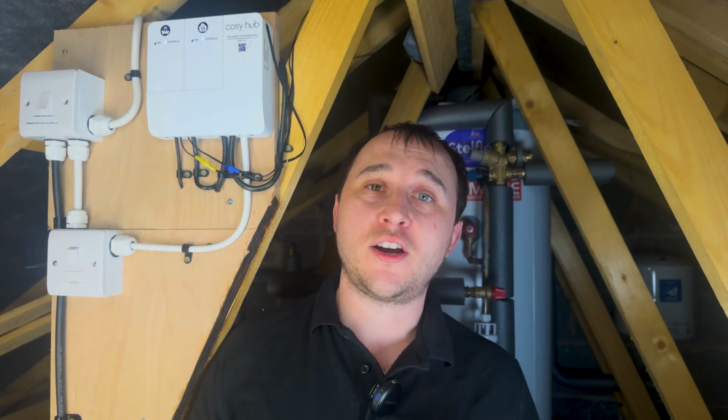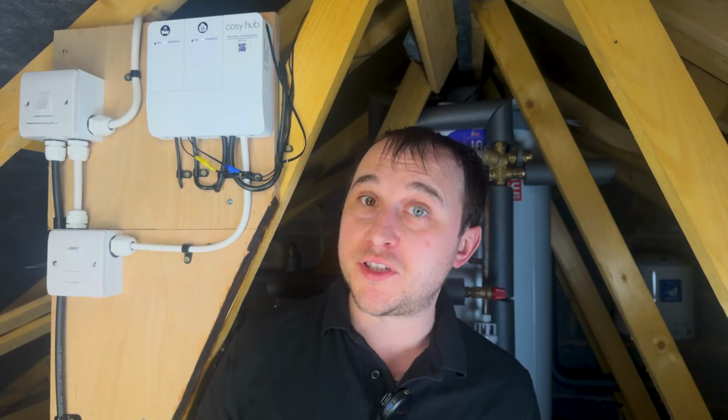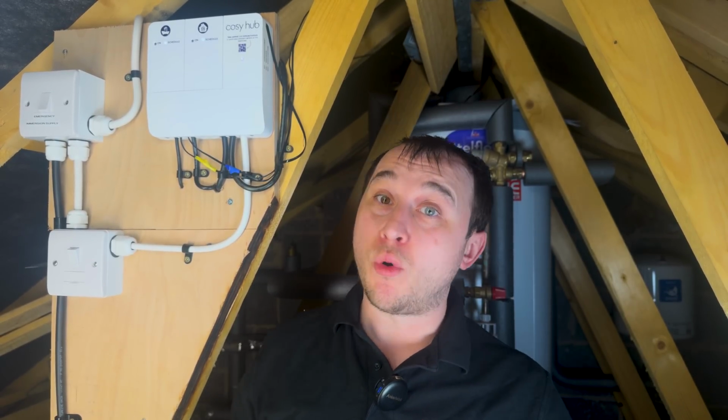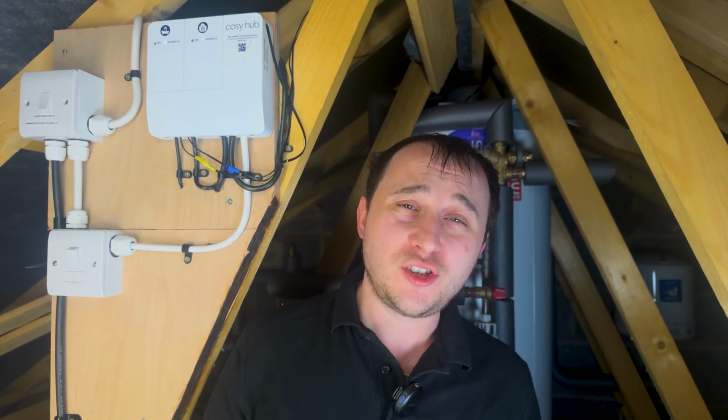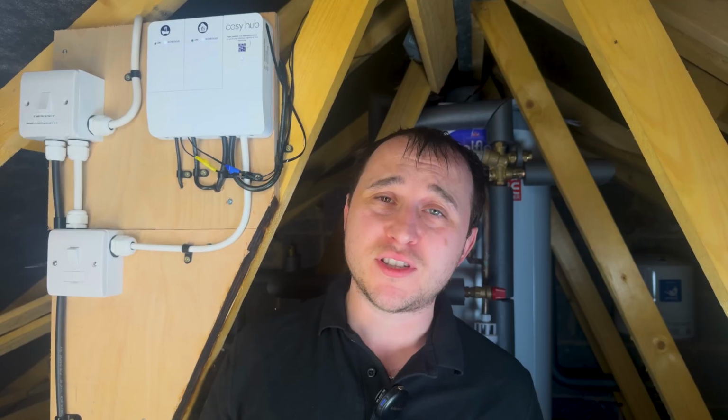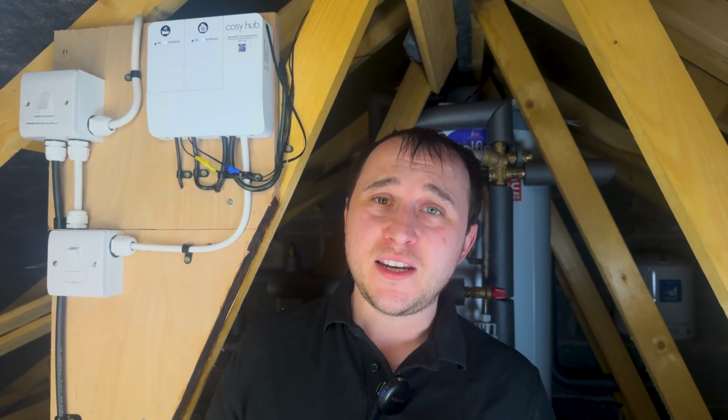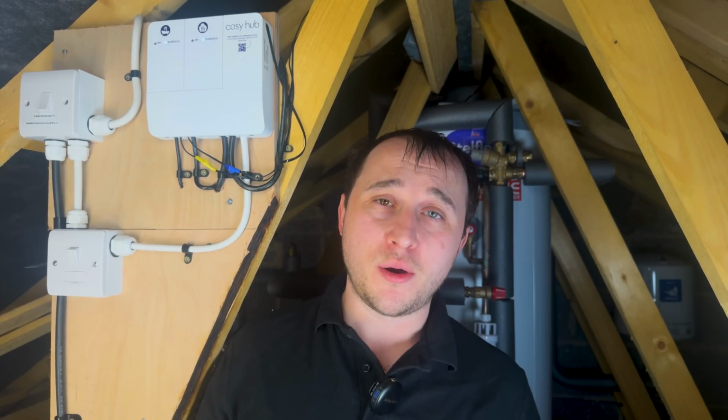Now, you can get your data on Heat Pump Energy Monitoring without the flow and return temperature, but with the flow and return temperature, you can work out various things like what the flow and return are doing, basically trying to optimize your system a little bit better on how it works, how low you can go. You should eventually be able to work out when it's doing defrost cycles. Now, to do this, you need some temperature probes on the flow and return.